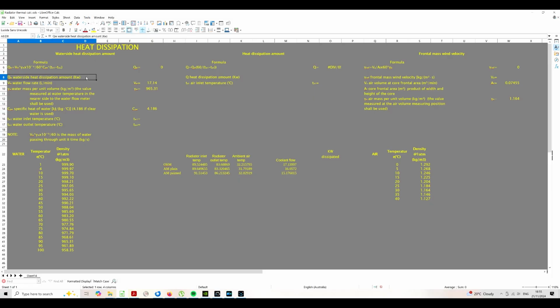Before we enter the numbers, we'll quickly cover the formula. Starting at the very top under the waterside heat dissipation amount: Q is the waterside heat amount in kilowatts, V is the water flow rate in litres per minute, and Y - I'll call it that for now - is the water mass per unit volume, basically the density at a given temperature.